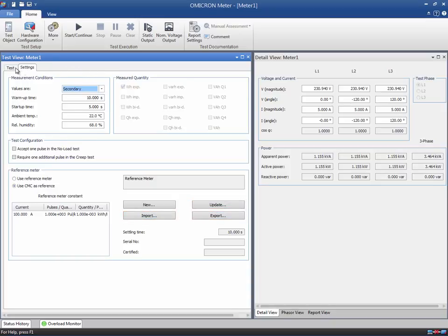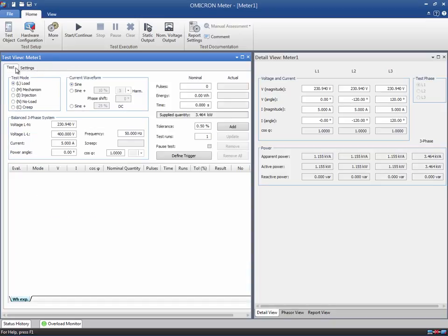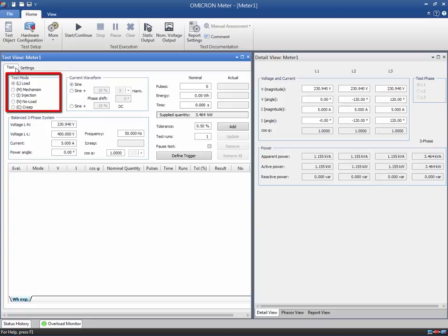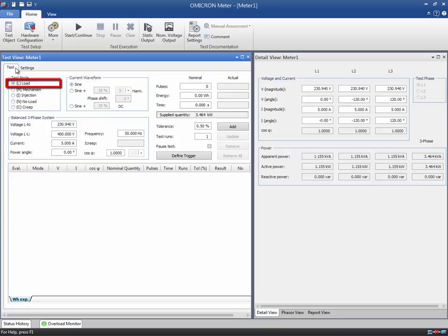The test tab contains the information for the test points to be executed. There are different test modes available depending on your application needs. In this example, we will apply a load test to check the meter's accuracy under normal operating conditions. The CMC test set outputs a set amount of energy until the meter feeds back the specified number of pulses. Check out the Help section if you want to see definitions for the other types of tests.